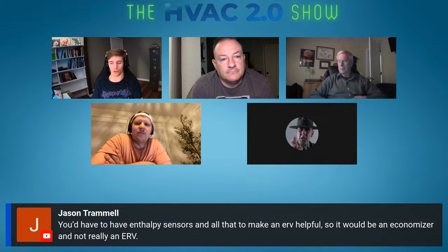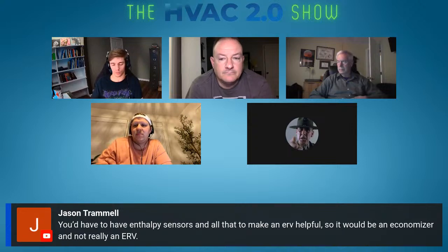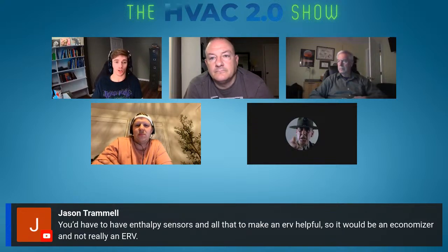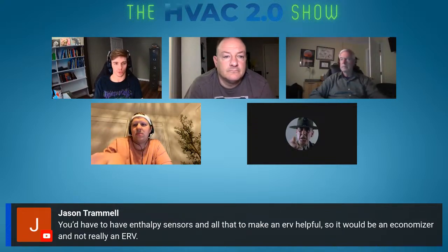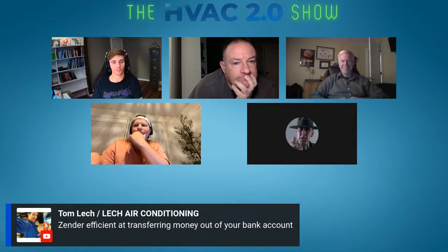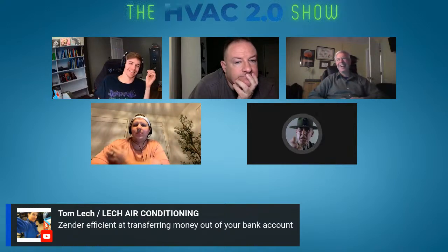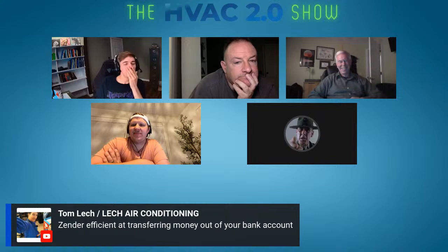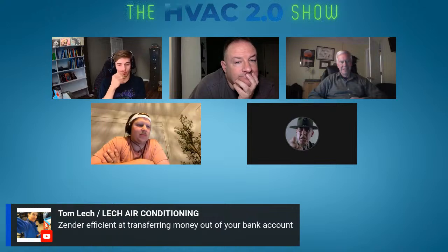even if you're throwing a lot of dehumidification at it. And so the question would be to look at his setup and really ask, okay, how much did this cost in total, and how much pain did that cost? And look at that number, and then go, okay, if I had to do it differently, could I do it for equal to or less? And I think you'd find the answer is yes. A Carrier 5-stage or Greenspeed with reheat dehumidification and a scuttle to outdoors might have been all he needed. It would have cost half as much as he spent.